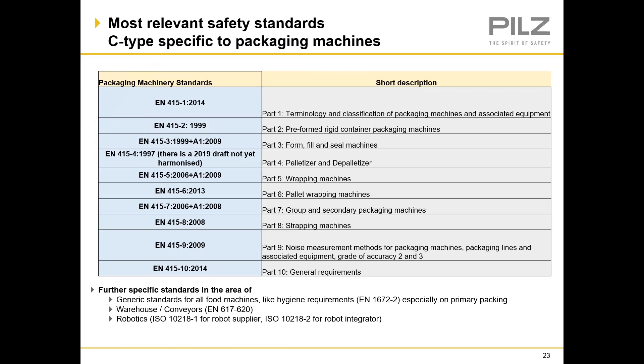The Type C standards for packaging machines are EN 415 parts 1 to 10. Part 1 is terminology and classification. Part 2 covers preformed rigid container packaging machines. Part 3 covers form fill and seal machines. Part 4 is palletizers and depalletizers. Part 5 is wrapping machines. Part 6 is pallet wrapping machines. Part 7 covers group and secondary packaging machines. Part 8 covers strapping machines. Part 9 is noise measurement methods applicable to all packaging machines. Part 10 is general requirements supplementing all other parts, particularly where new automation methods or robots are used.